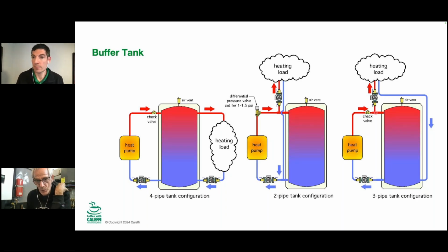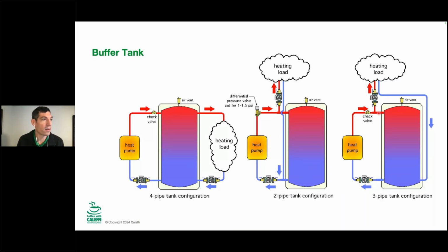Basically, we want the flow through this pipe to be no more than 2 feet per second when everything's running. So for that pipe, you have to add up the GPM of all your loads and then look at a piping chart and say, okay, I've got 18 gallons a minute, I need 1.5 inch copper pipe or 1.5 inch steel pipe to assure I get my separation here. So yeah, the very technical term being short and fat. That's what we're looking for in that little span.